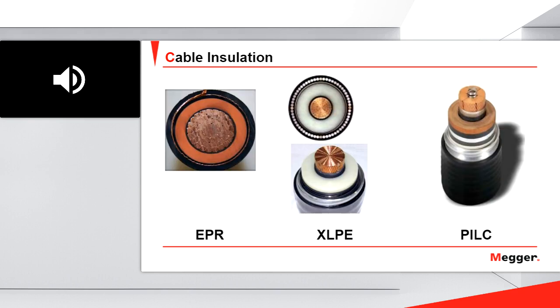Talking about the types of insulation, mainly today we have only two types: the polymeric or plastic insulations, as in the case of EPR or XLPE, and paper insulated cables. From the point of view of fault location, that makes a big difference. For instance, let's say I have a fault in an EPR or XLPE cable, and that fault is a pinhole, a perforation in the insulation of this XLPE cable. The hole will be filled with dust, maybe water, or air.